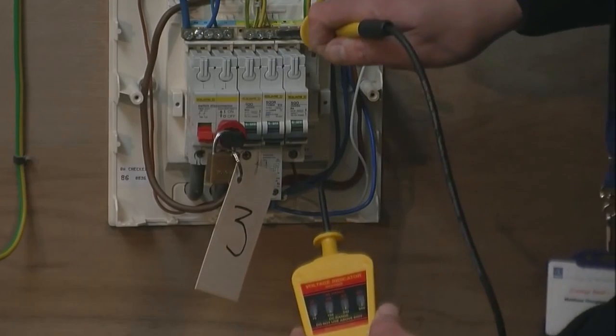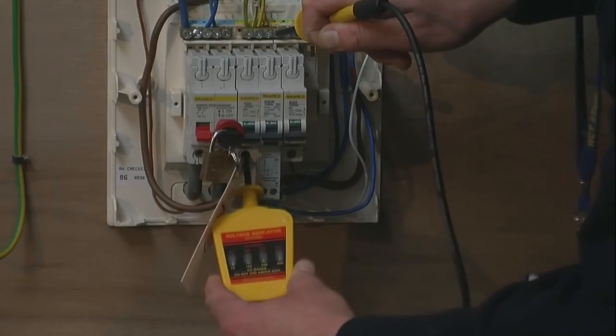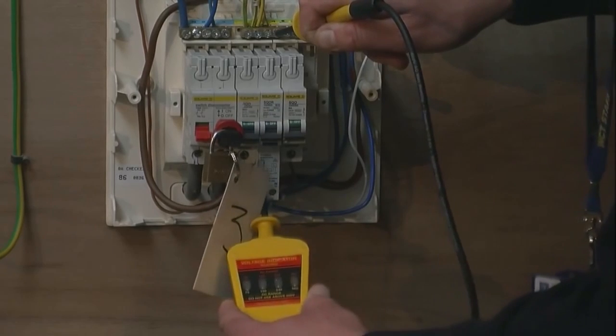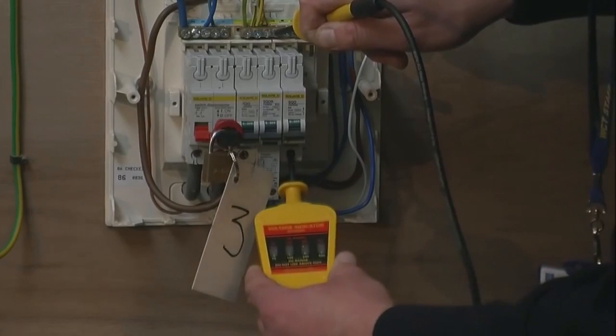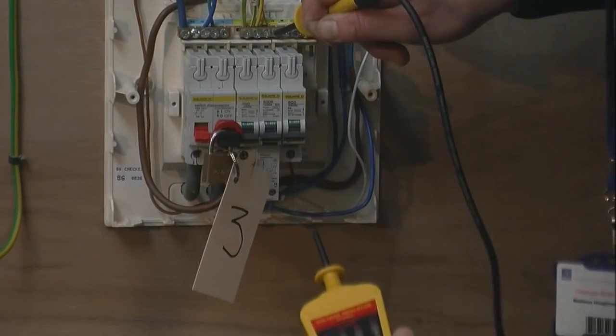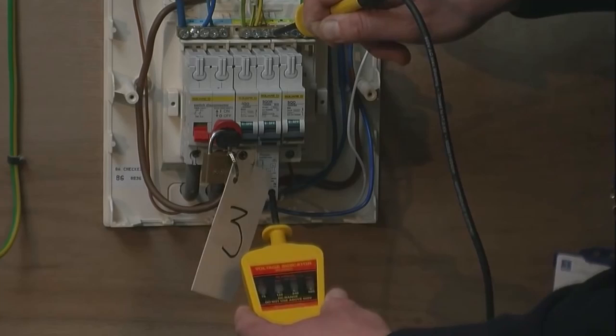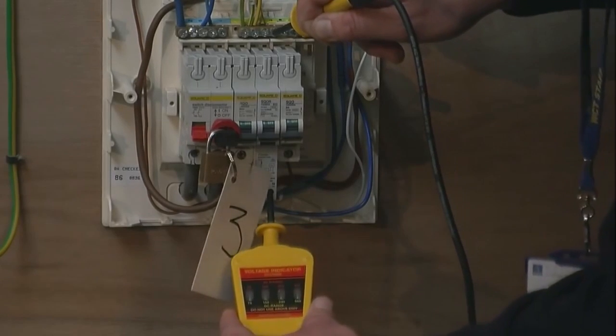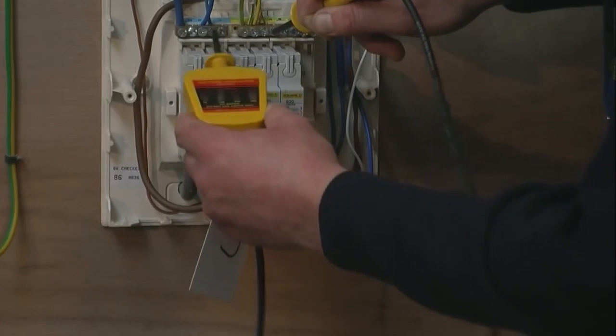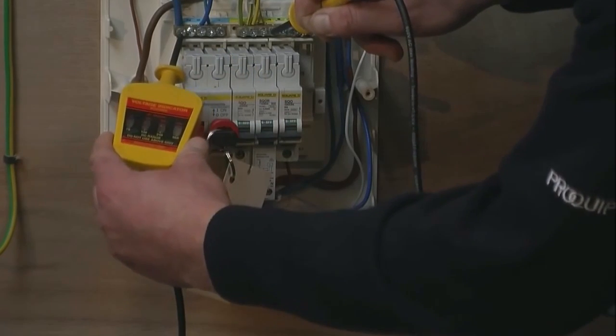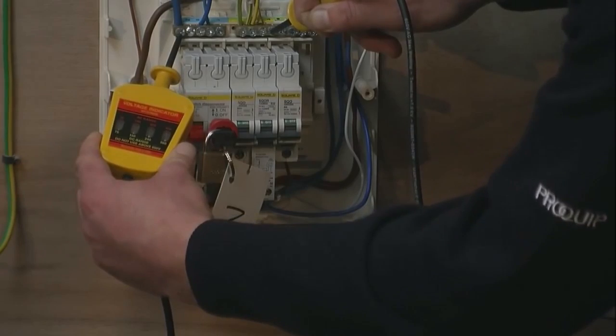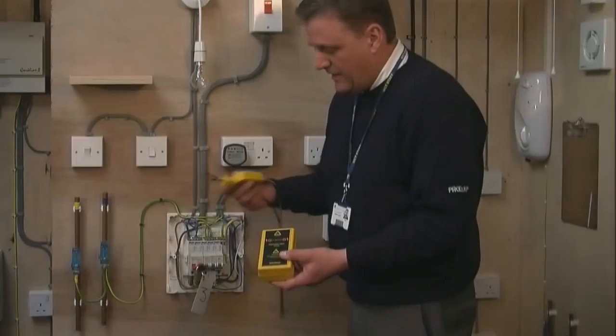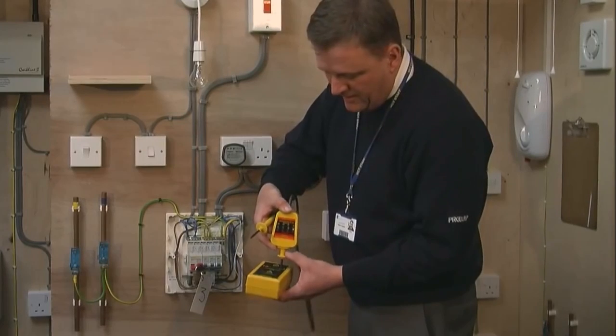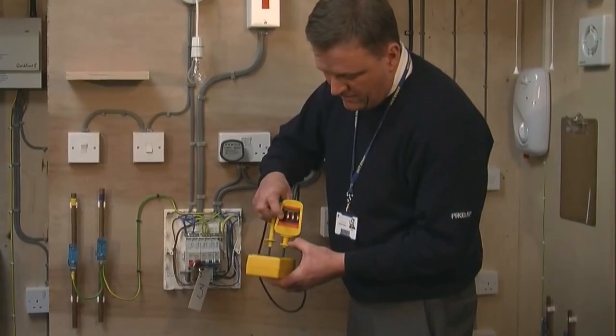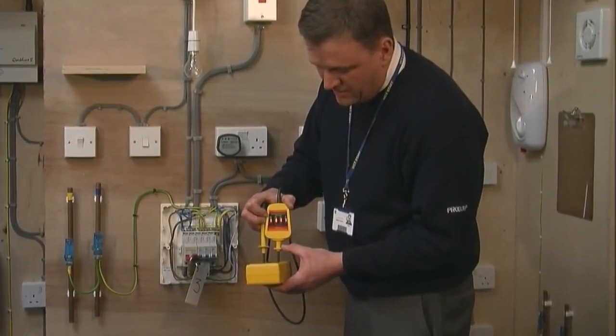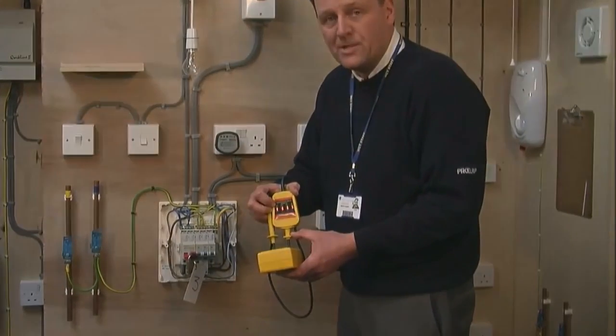We then go onto the earth terminal block and do exactly the same. As you can see, the lights are not lit. We then go on to the neutral block, or in this case the RCBO neutral, and then finally onto the neutral block here, and as you can see, none of the lights are lit. We then take our voltage indicator, we go back to our proving unit and retest the voltage indicator. This shows that the voltage indicator wasn't damaged during the test procedure.